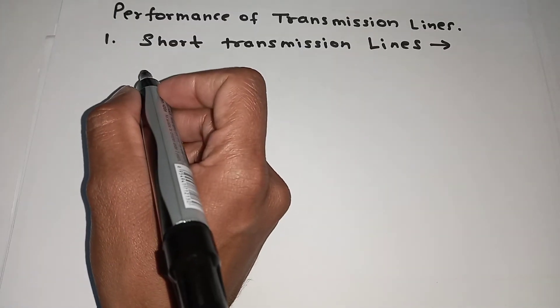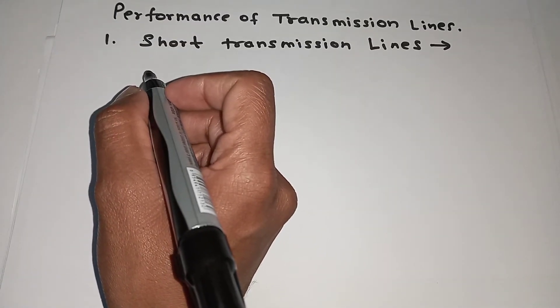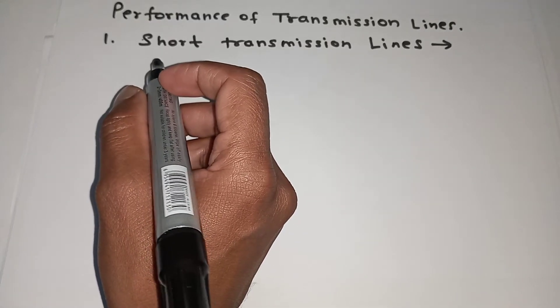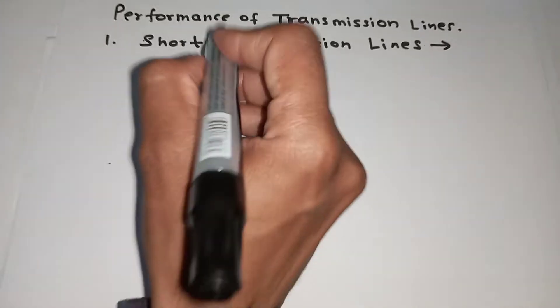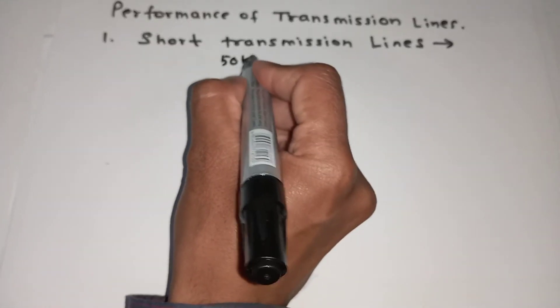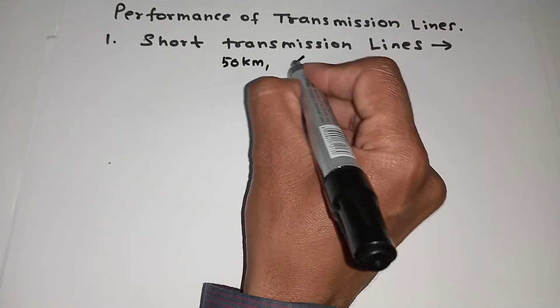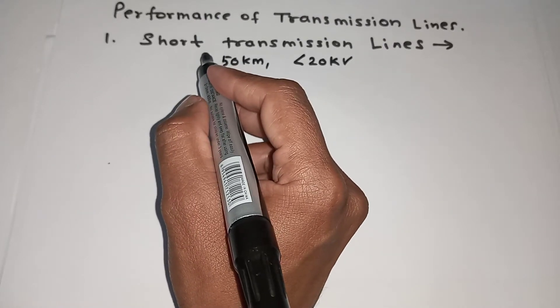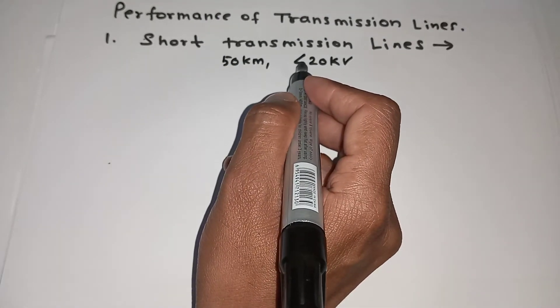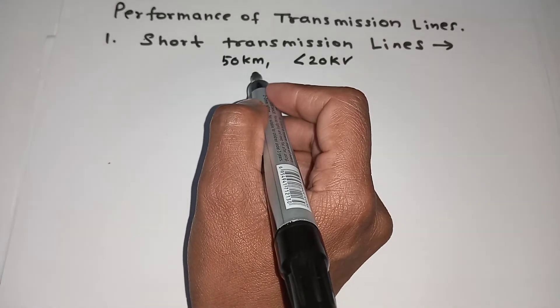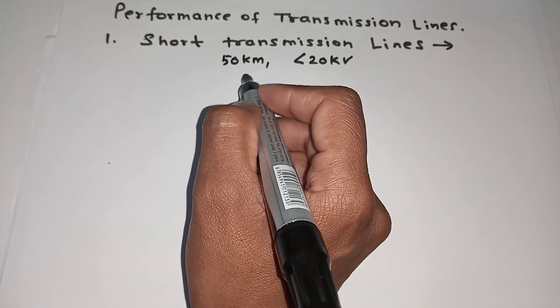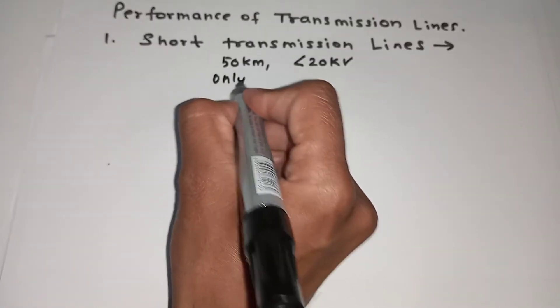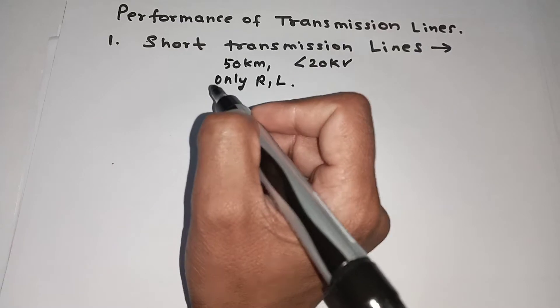Hello friends, today we'll discuss the performance of a transmission line. First, we will discuss the short transmission line. The range of a short transmission line is up to 50 kilometers and the voltage is less than 20 kilovolts. Because the length and voltage are smaller, there are no capacitance effects — only resistance and inductance are taken into account, so only R and L.